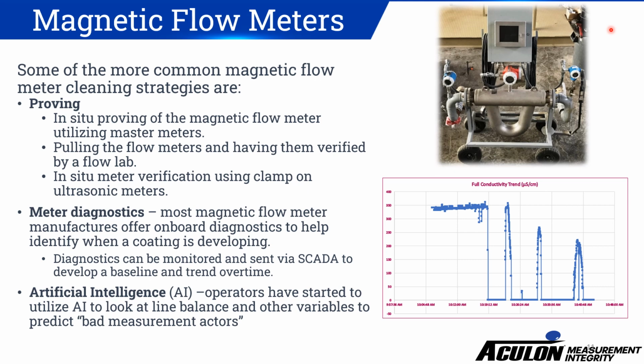It is important to note that the magnetic flow meter under test is typically more accurate than the ultrasonic master meter. So this method is used to determine if there has been a change in the magnetic flow meter's baseline performance, or to determine if the magnetic flow meter's accuracy is outside of the accuracy of the master ultrasonic meter, which is typically about plus or minus 3%.